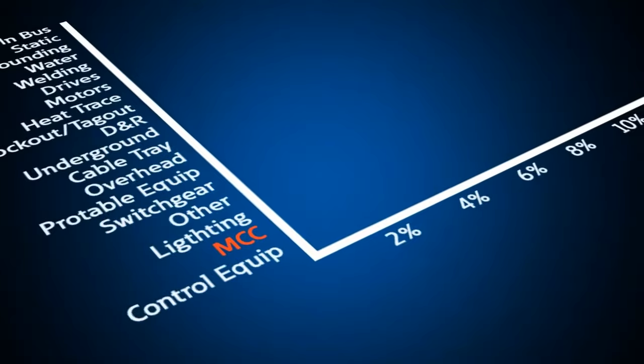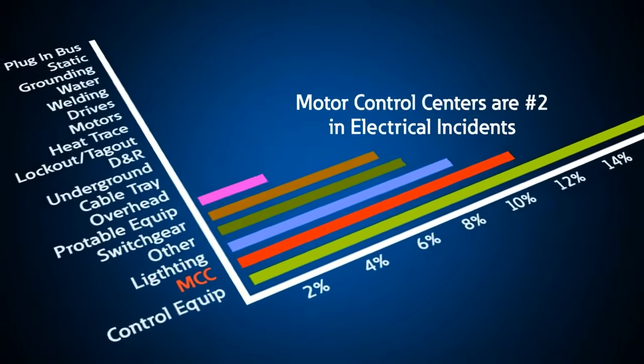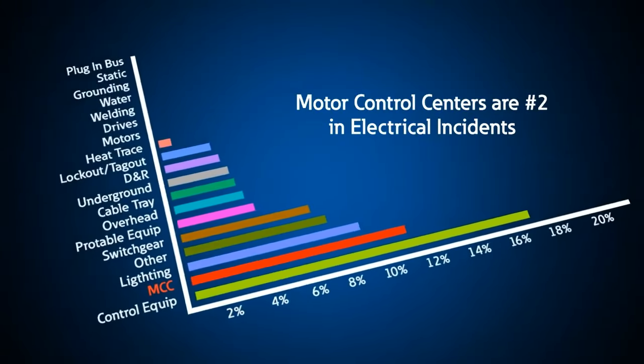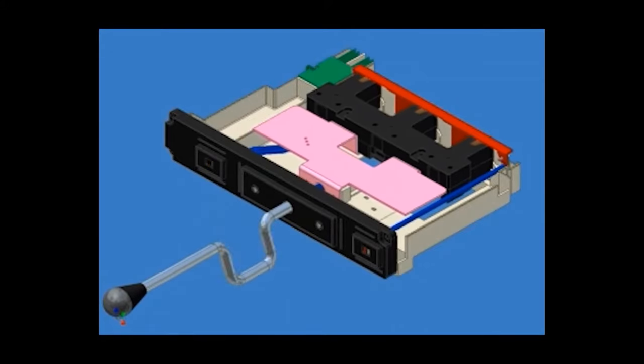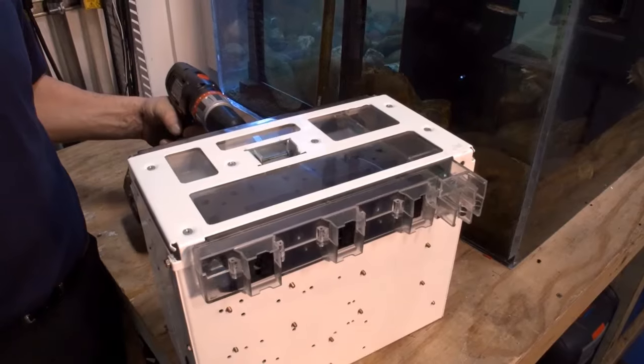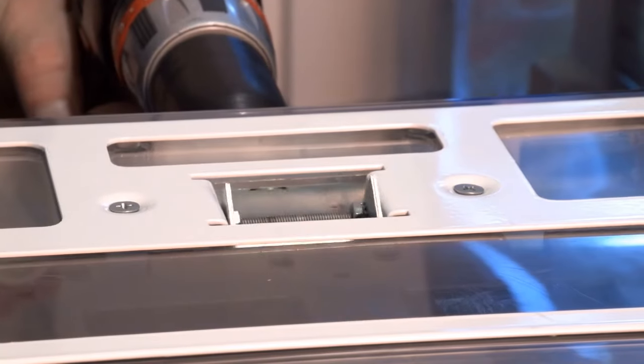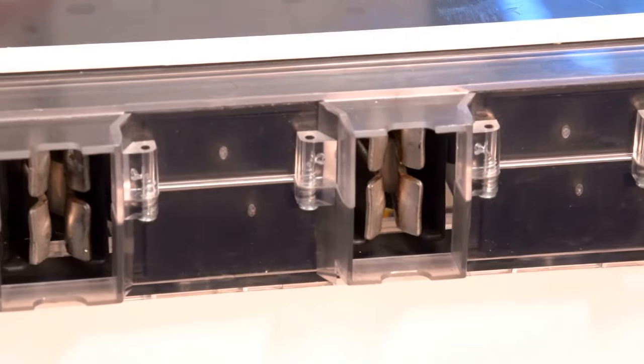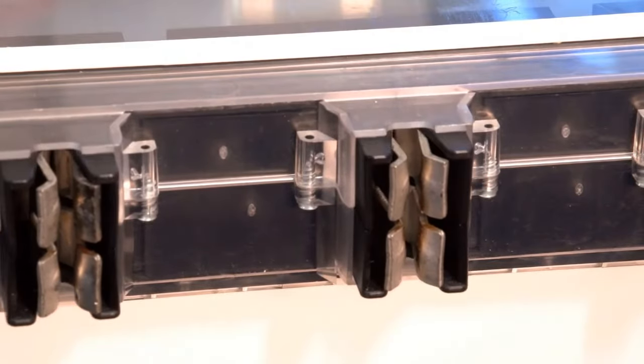One of the most common times for an arc flash event to occur is when adding or removing a bucket in a motor control center. This flash guard bucket can be added or removed with the door shut, with a local or remote operator protecting the worker until the bucket is safely removed from the energized bus. This FlashGuard MCC takes the procedures and guesswork out of your hands, only allowing the disconnect from live bus operation to be done exactly the same way each and every time.